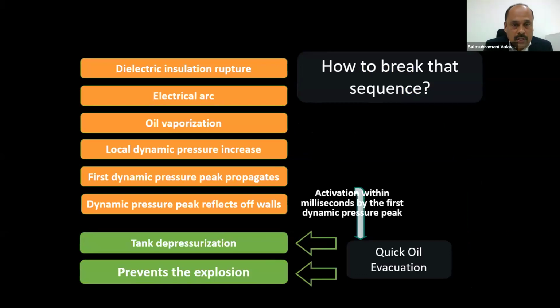But when you have a depressurization chamber, what is a depressurization chamber? There will be a disc in it, fixed at a particular pressure, a particular bar, where it will break. The moment the pressure increases, it goes and touches the depressurization rupture disc. When the pressure reaches a particular bar, the rupture disc breaks, allowing the oil to get into the oil gas suppression tank. When the arc happens, the temperature also increases, and there will be gases. The gases also will be put into the oil gas suppression tank. From there, it will be evacuated to the atmosphere, thereby preventing the explosion.